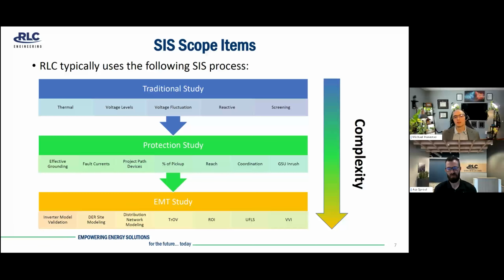So first, we're going to be taking a look at the traditional study elements. These are the elements that you will typically find in most system impact studies. It'll cover things like thermal, steady state voltage, voltage fluctuations, reactive power, and some of the screens. We'll then look at protection evaluations, and that might include effective grounding, fault current evaluations, project path devices, percent of pickup, reach coordination, and GSU inrush.